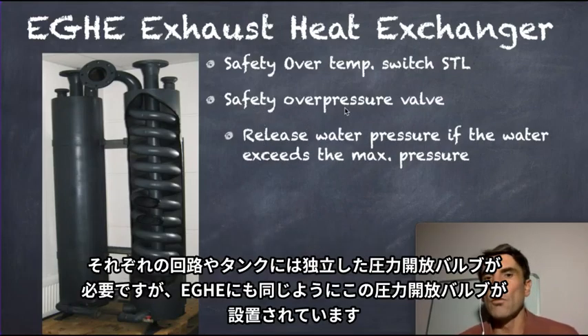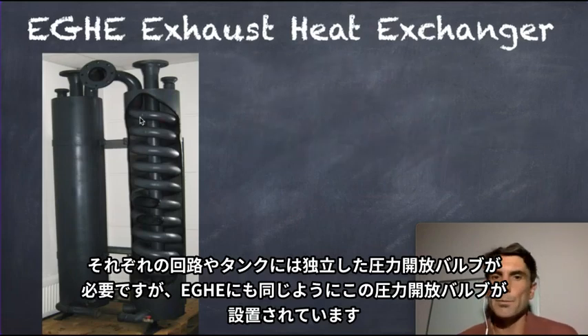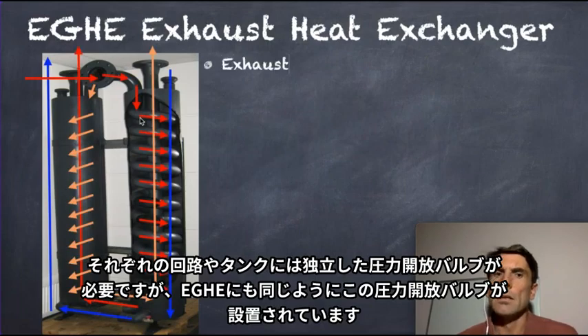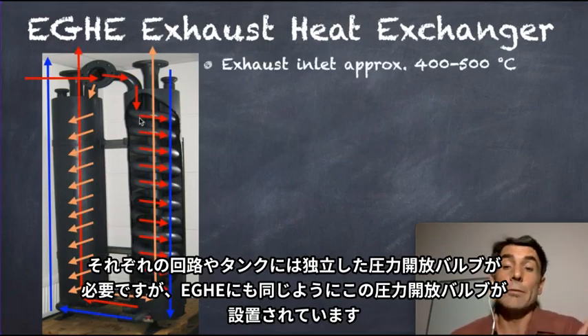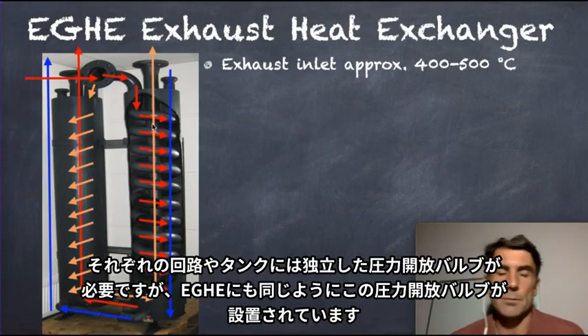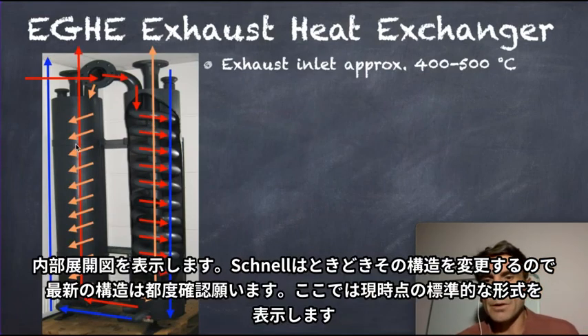So we will have an overpressure release valve. Always, on a separate cycle or on tanks, you need this overpressure valve. If the pressure in the tank exceeds a maximum pressure, the valve will release the water and reduce the pressure. So we have here a little bit of flow. Please note, Schnell sometimes changes the design of the flow for different versions. So this is a standard version.